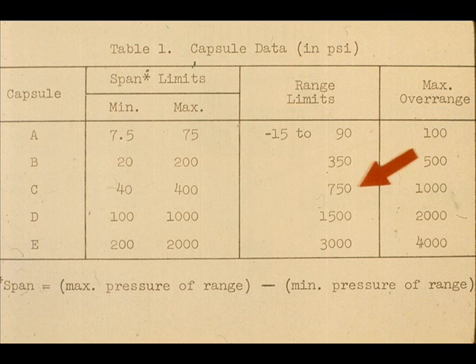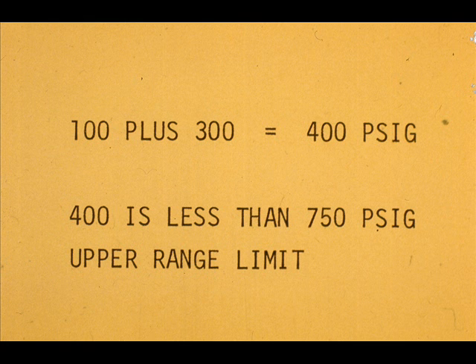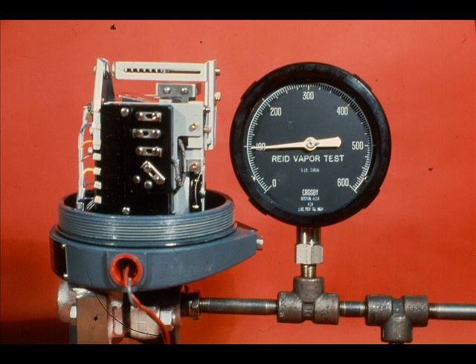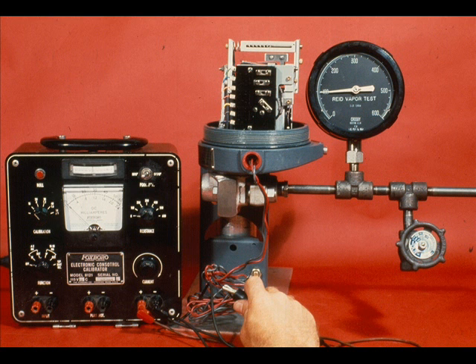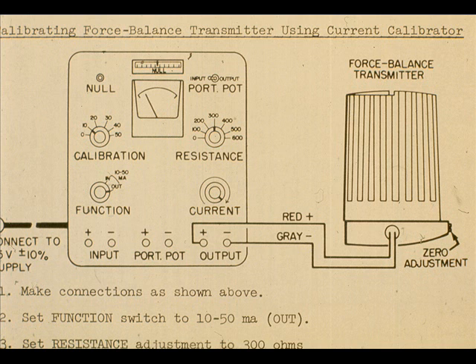The upper range limit for capsule C is 750 PSIG. Therefore, it is okay to use for the range 100 to 400 PSIG. We are finally ready to calibrate. Apply 100 PSIG to the transmitter. Connect the Foxboro 8121 or equivalent calibrator to the transmitter. Set it for calibrating a 10 to 50 milliamp force balance transmitter.